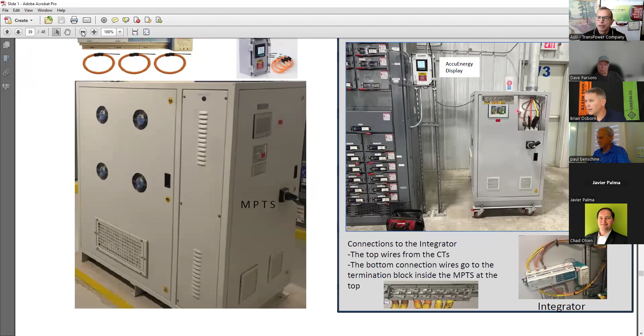Here's another picture which I think is a very clean installation - another factory, again they got the struts, the AccuEnergy unit. This is what we want installed like right now, because this gives room for watching what is happening. Then the MPTS arrives and they install the MPTS, and you continue to see the change in voltage, current, power factor, kVA, kW, kVAR, and harmonics. You have a before MPTS and after MPTS, a beautiful graph that you can see.